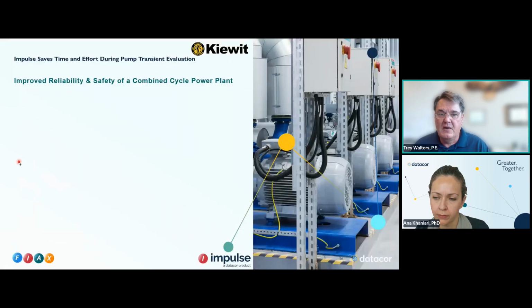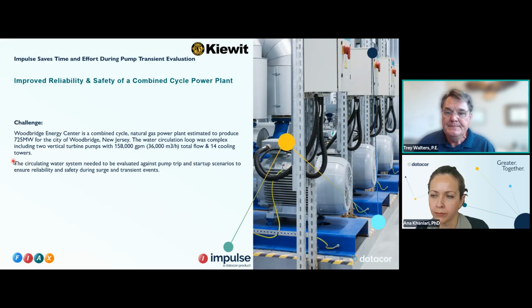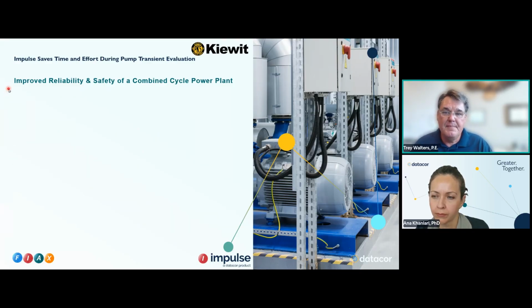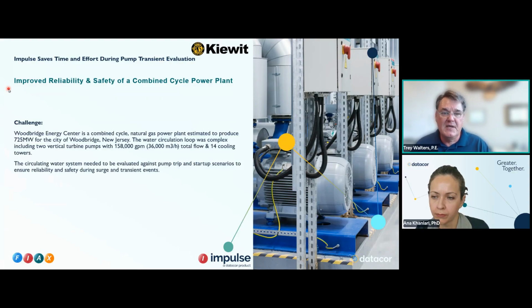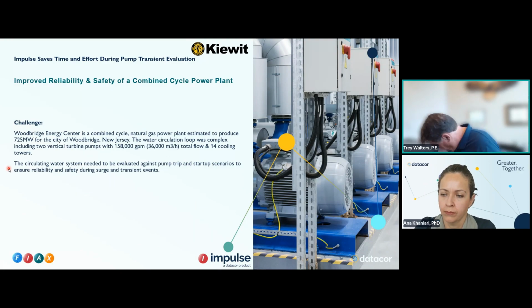A few years before that, one of our customers at Kiewit did some modeling on it. Right now we're going to focus on what they did on the condenser cooling water system. They wanted to improve reliability and safety of the combined cycle power plant. The challenge: it's a combined cycle natural gas power plant, 725 megawatts as I mentioned before. The water circulation loop was complex and included 2 vertical turbine pumps with 158,000 GPM, 36,000 cubic meters an hour, total flow, and 14 cooling towers. The circulating water system needed to be evaluated against pump trip and startup scenarios to ensure reliability and safety during surge and transient events.